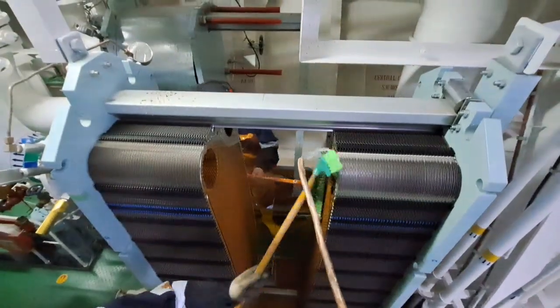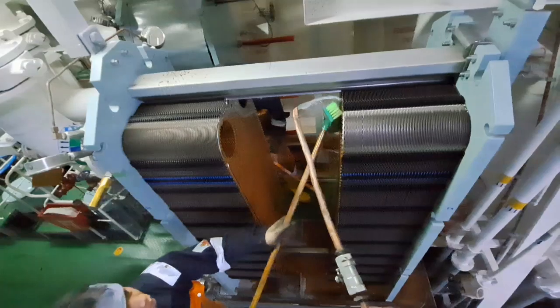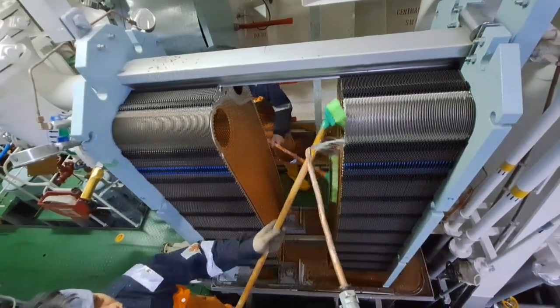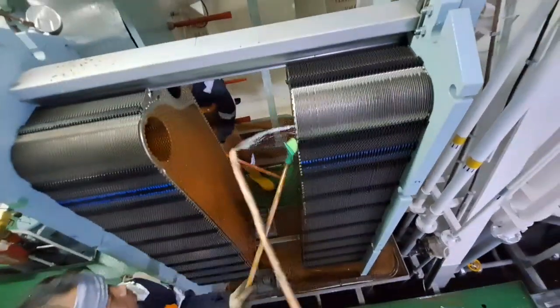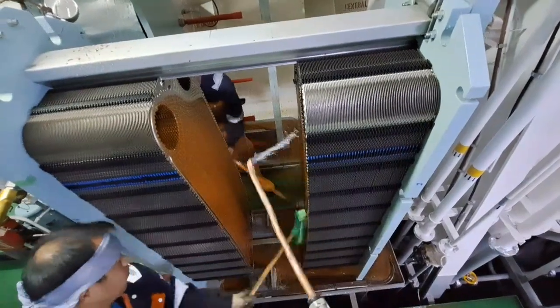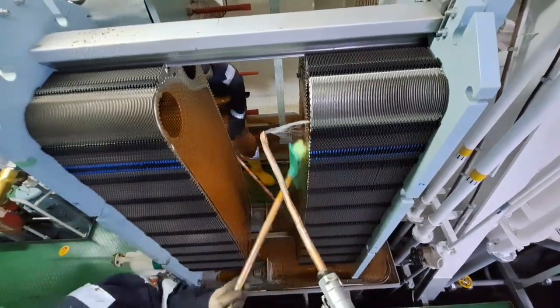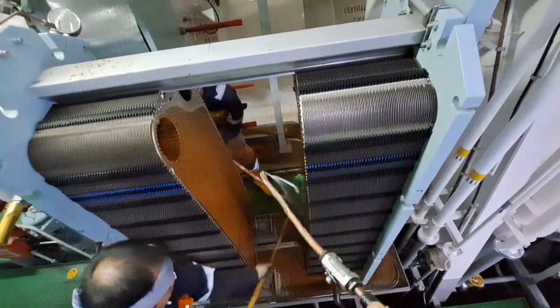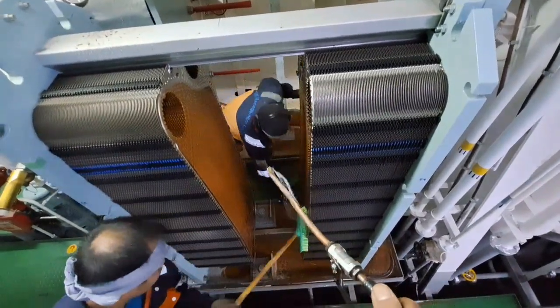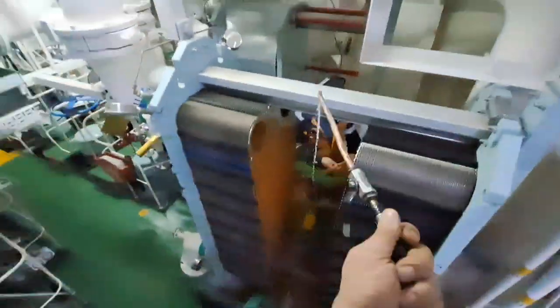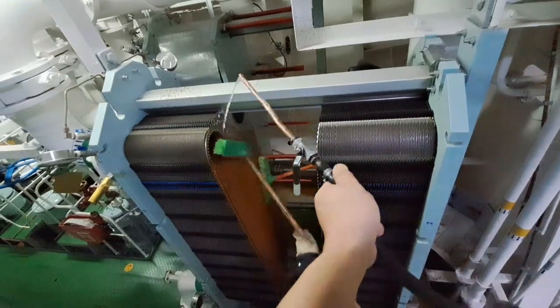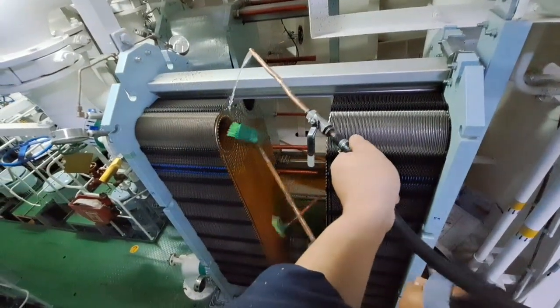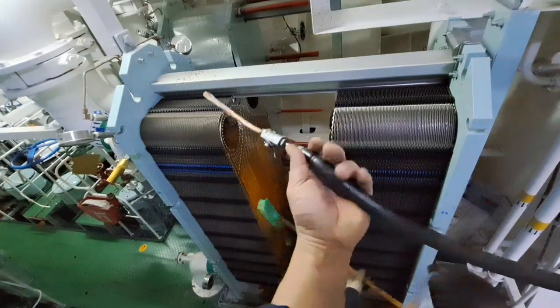With a plate heat exchanger, heat cuts through the surface and separates the hot medium from the cold. Thus, heating and cooling fluids and gases use minimal energy levels. The theory of heat transfer between the medium and fluid is that heat is always transferred from the hot medium to the cold medium.